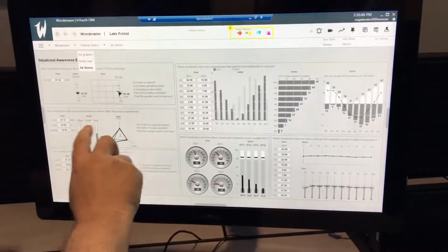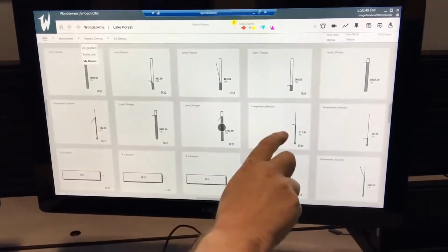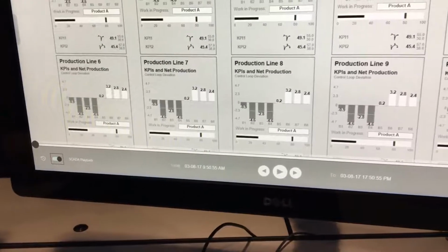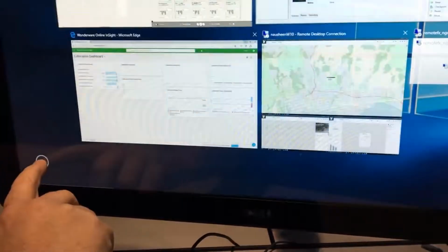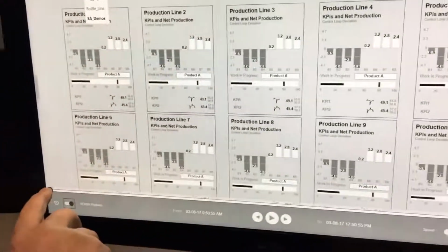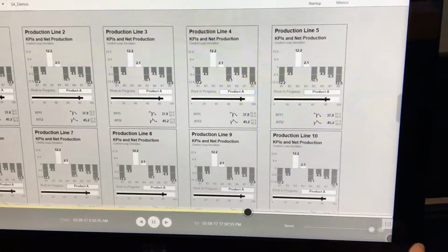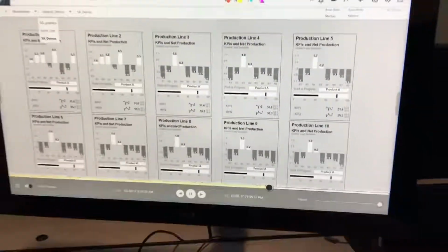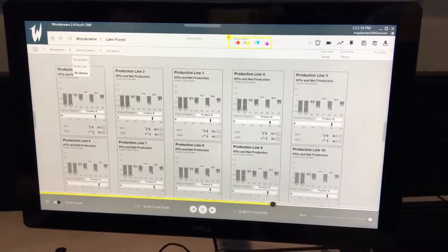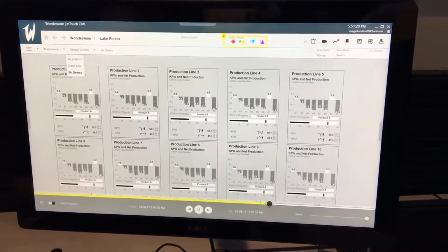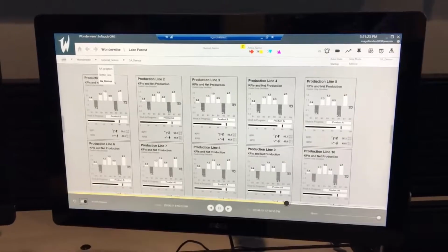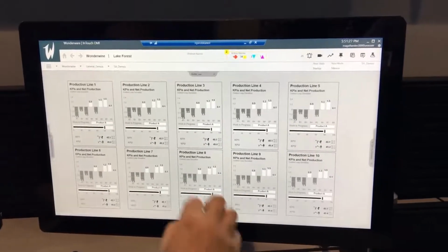Wanted to show real here we're gonna go to dashboards, and then we're gonna play back some data. So we're gonna go here, and we're gonna take this dashboard, bring up the SCADA playback. So right now when I go to SCADA playback mode, the system is frozen. Move it to a time, hit the playback button, and change the speed. So right now, it's playing back the data from the historian and not live. So that's historical SCADA playback feature. This works on any graphic at any time. So disabling it goes back to runtime data.